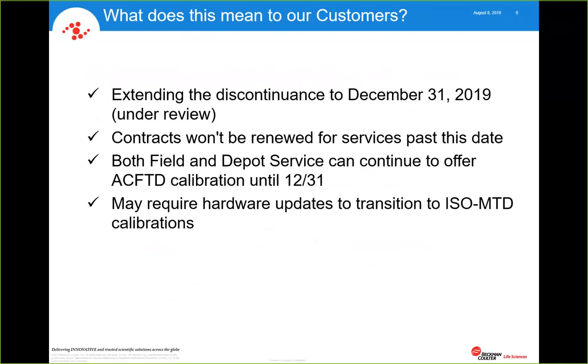So we're extending the discontinuance of the AC fine test dust calibrations till the end of this year. Beyond that, we're going to be offering ISO medium test dust calibrations for the commercial products. Contracts apparently won't be renewed for service past that date. Both our field and depot service can continue to offer AC fine up until, again, the end of this year. And it may require hardware updates to transition to the ISO medium test dust calibrations, and that's one of the things I'm going to talk about further on in this presentation. How does this affect our old customers? What do they need to do to change their equipment, upgrade their equipment to be able to accommodate the new medium test dust calibration?